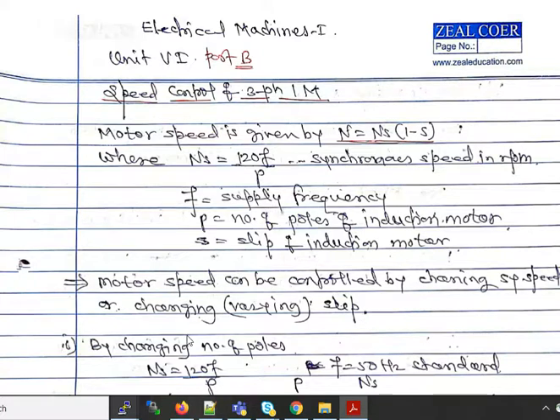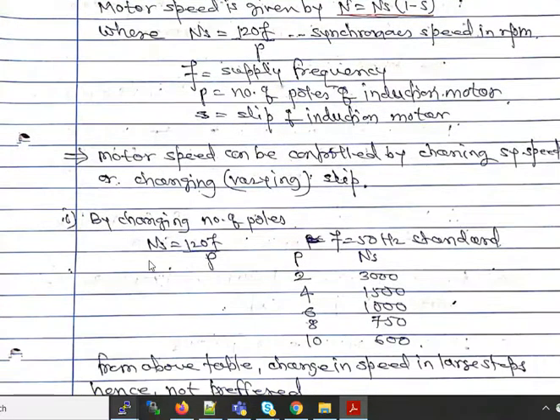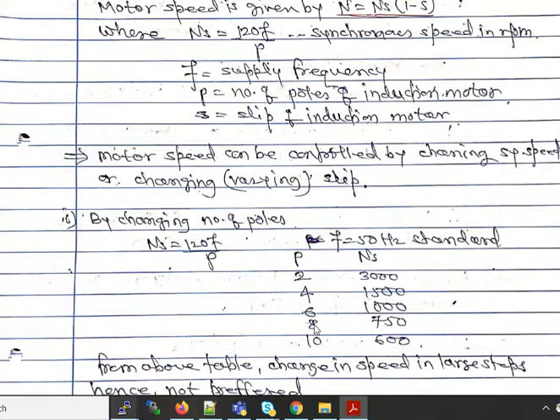Now let us consider speed control by changing the number of poles. Since ns = 120f / p, the speed is inversely proportional to the number of poles. At standard frequency 50 Hz, the number of poles are always even numbers. When p = 2, ns = 3000 rpm; p = 4 gives 1500; p = 6 gives 1000; p = 8 gives 750; and p = 10 gives 600 rpm.